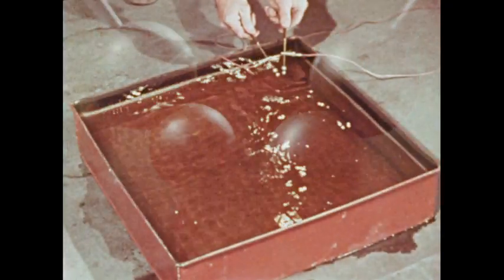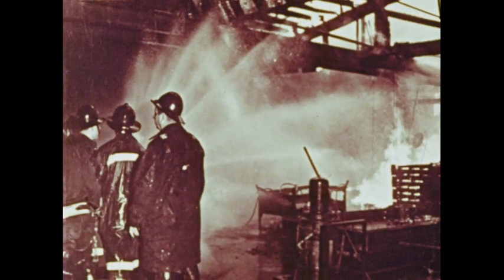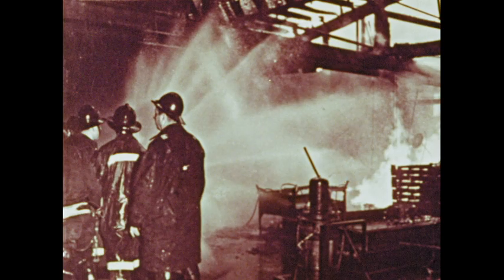Let's run the electrodes from the static machine and hold them over a pan of liquid. You're not likely to see the spark when it occurs, but there's no question about the result produced. How can we prevent static sparks at processes where flammable liquids are handled? One way is to humidify the air. This puts a thin, invisible film of moisture on all objects, which drains away the static as soon as it forms. A dangerous charge cannot accumulate.